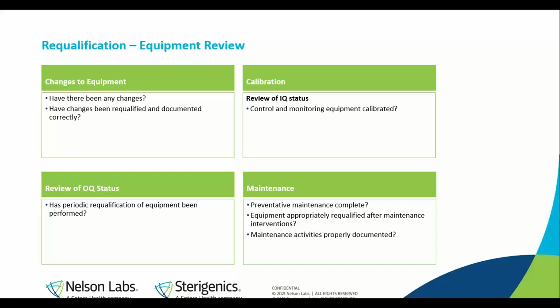The first phase of the annual review is to evaluate how the equipment has been performing. So firstly, we're going to look at changes to the equipment and determine, have there been any changes to the equipment? Have the changes been requalified, and has that documentation been provided? The second phase of the equipment review should cover any calibration. This would absolutely include a review of the installation qualification of the chamber or other monitoring equipment. And it includes any calibration of the control and monitoring equipment associated with the equipment. Next, a review of the OQ status should be performed. Has a periodic requalification of the equipment been performed? How does that affect the process?